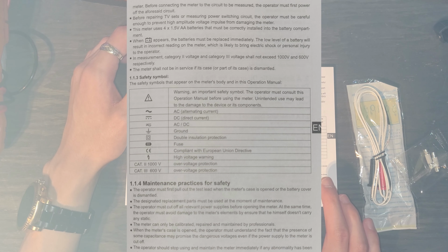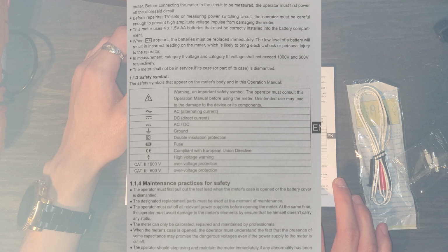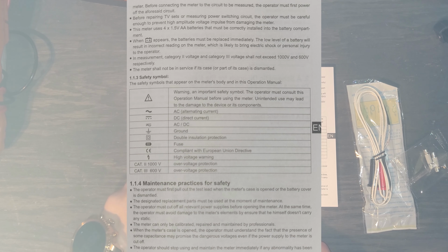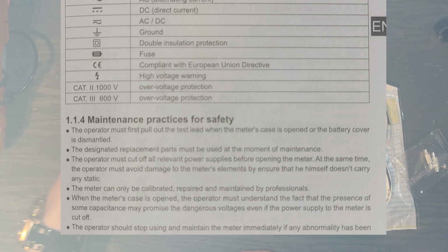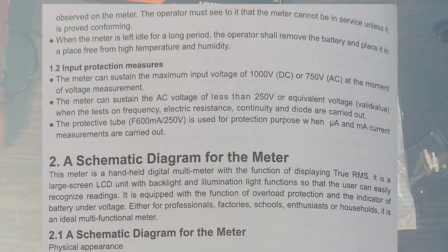The meter can only be calibrated, repaired, or maintained by professionals. When the meter's case is open, the operator must understand the fact that the presence of some capacitance may promise dangerous voltages even if the power supply to the meter is cut off. So everything has a little bit of parasitic capacitance, and since parasitic capacitance can cause harm, just be aware of that. The operator should stop using and maintaining the meter immediately if any abnormality has been noticed. The operator must see to it that the meter cannot be in service unless it is proved conforming. When the meter is left idle for a long period of time, the operator shall remove the battery and place it in a place free from high temperatures and humidity.